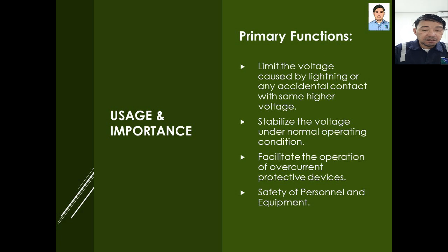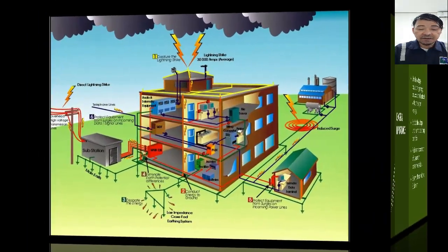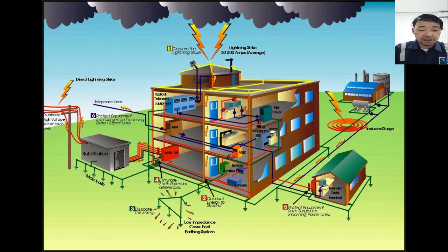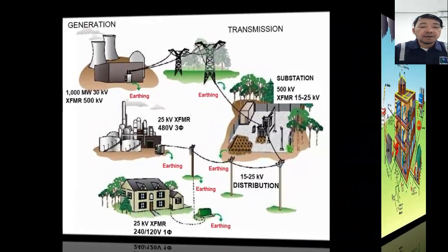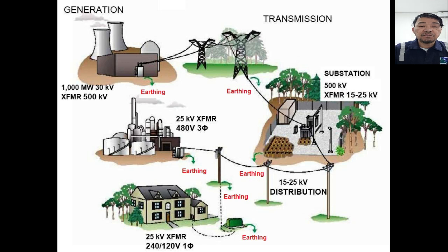Here are the following usage and importance. We have the primary function: limit the voltage. When a lightning protection and grounding network is in place, the strike is intercepted and directed to the ground without impact to the structure, electrical installation, as well as people in the area. Stabilize. Grounding establishes a reference to the earth from the system and stabilizes the voltage to ground during normal operations.